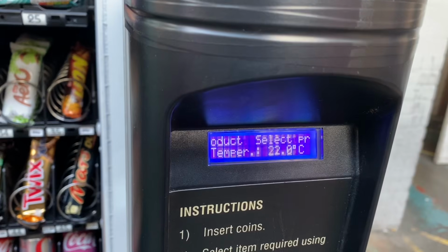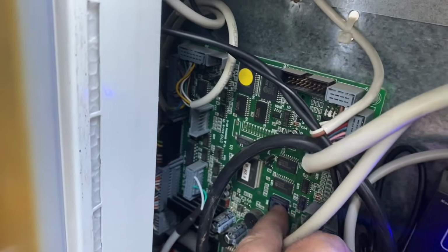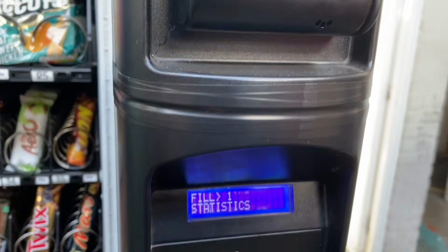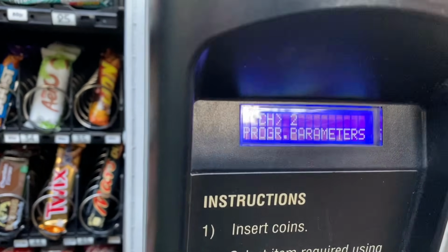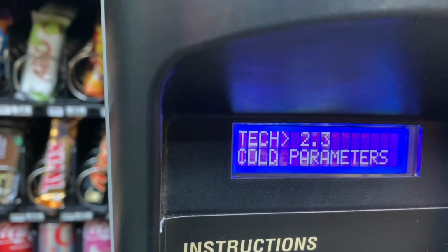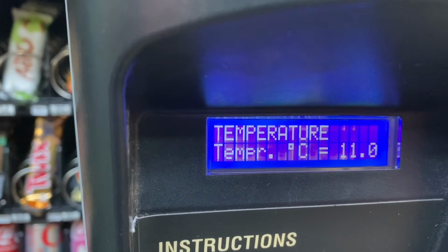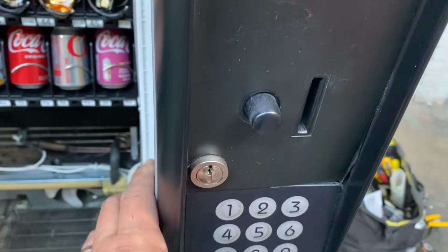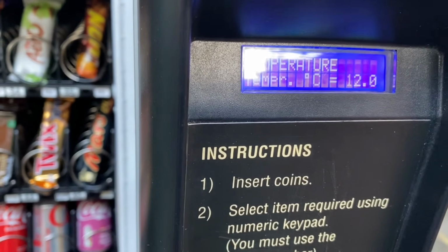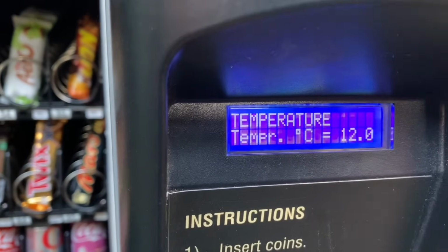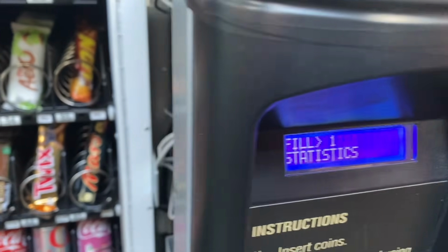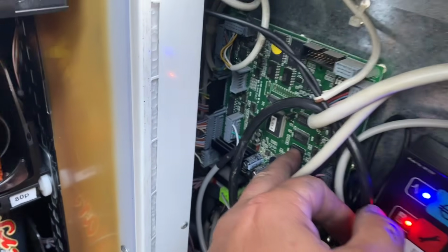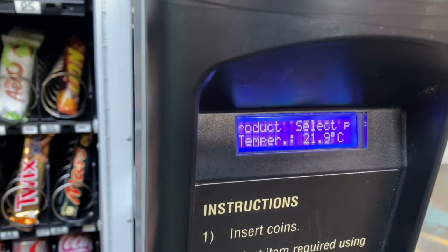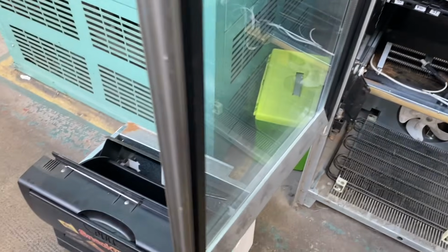Excellent. Now that temperature should start to come down once you get the bucket back in, because we've had the door open for a while, so obviously the temperature inside the cabinet's gone high. And we're just going to have a look into the menu of cold parameters, and we can have a look at the temperature quickly to see what the temperature is set at. The lower the temperature, the harder the chiller needs to work. So most chillers are quite happy to run at 12 to 13 degrees, which is cold enough for the drinks to chill down, and it's not too low that the compressor has to continuously work hard to get down to that temperature. So it just prolongs the life of the chiller units. And that's it. Once you've done that, put the bucket back into the machine, and yeah, everything's sorted.